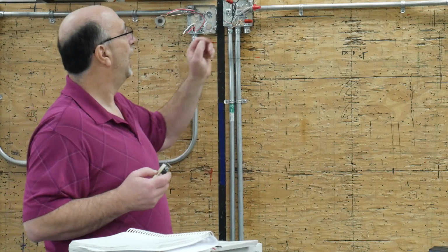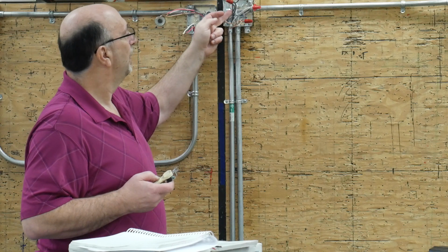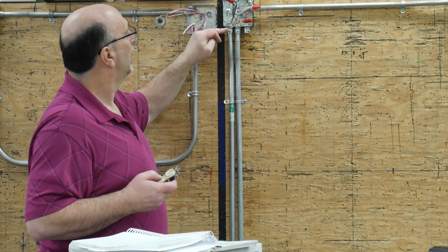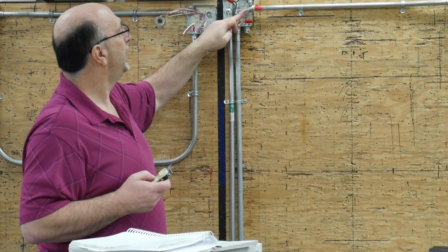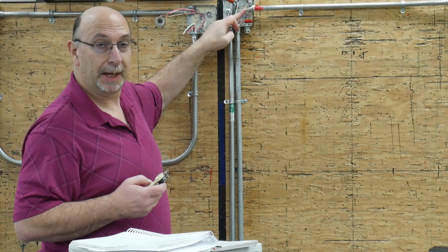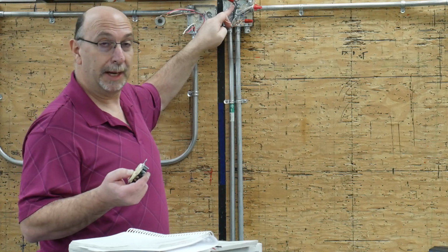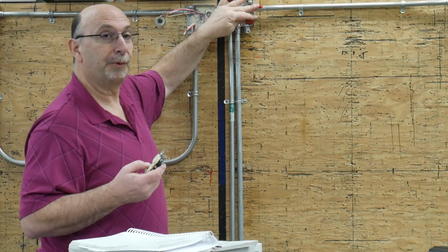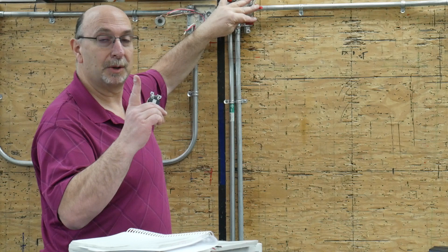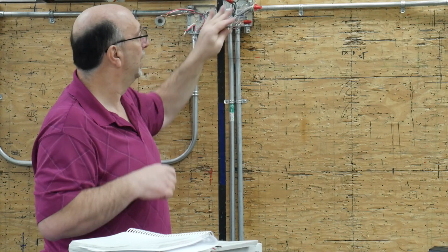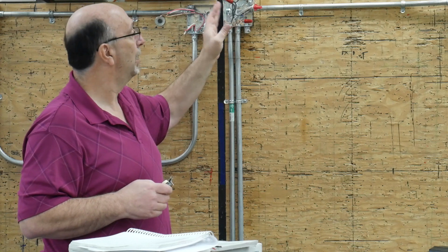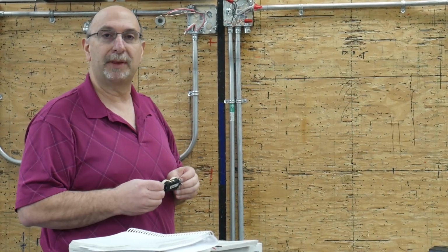However, over here on this example, because we have 3 white conductors, that counts as 3 conductors. 3 black conductors, that counts as another 3. We're up to 6. 3 wire nuts, that counts as 1 more, so that's 7. So if you ever have to do box fill calculation, it's 7 conductors multiplied by whatever the wire size table is. Anyway, we'll come back shortly with a calculation.